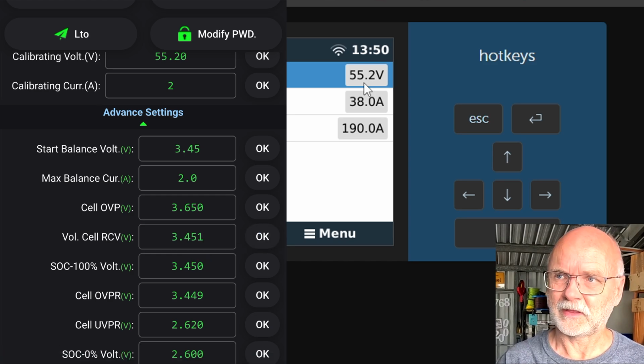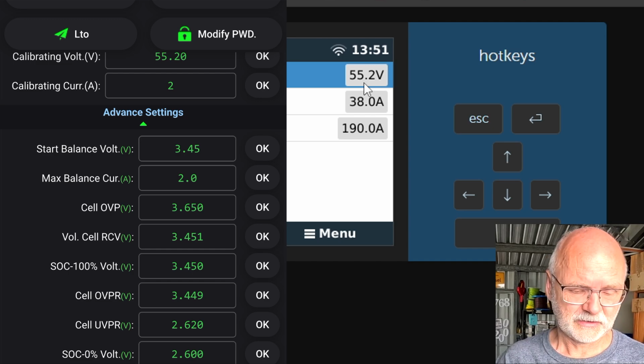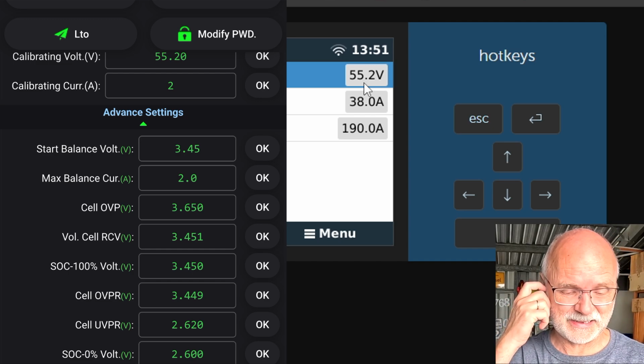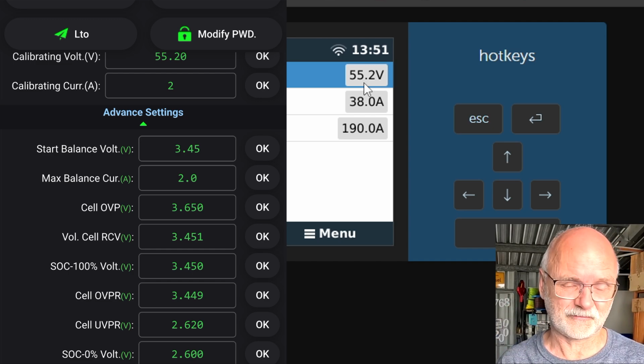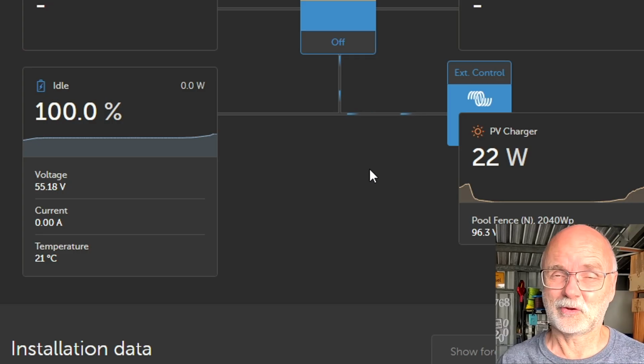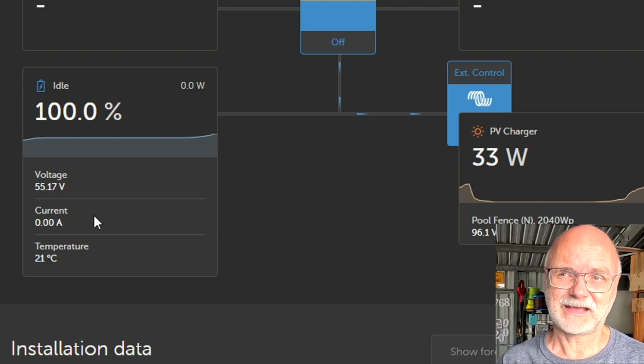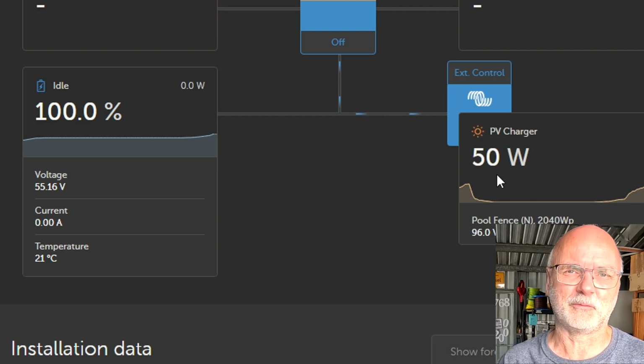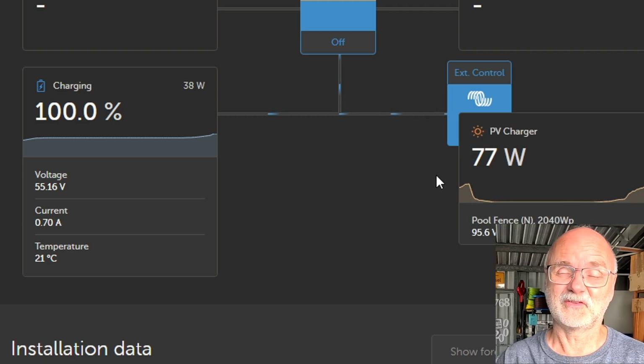And then it goes down to 55.2. It is still listening to the RCV settings of the BMS. And because we have reached 55.2 volts now, the batteries are fully absorbed, fully saturated, current goes down to 0, and we're only charging with about 50 watts into the battery. So this battery is now really 100% charged.